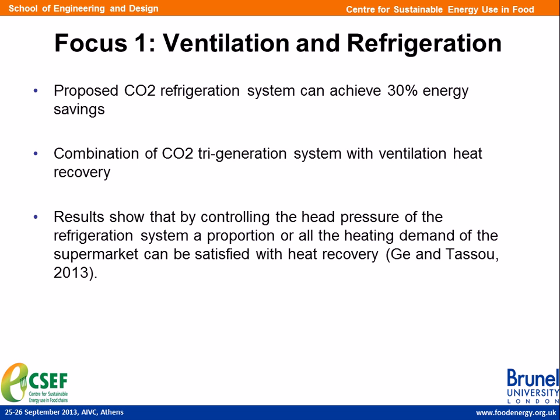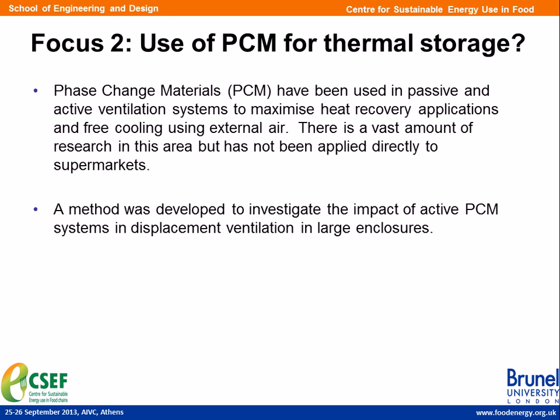Now, the combination of this CO2 trigeneration system with ventilation heat recovery is another step that we are investigating, and preliminary results show that by controlling the head pressure of the refrigeration system, a proportion or all of the heating demand of the supermarket can be satisfied with heat recovery. So this is one of the areas, which I wrote there as focus 1, that we are trying to concentrate our research on. Focus 2 is the use of phase change materials for thermal storage.